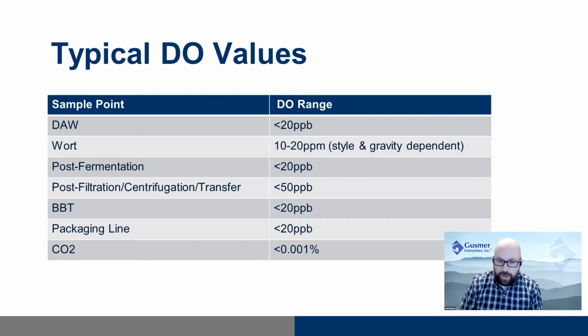So for deaerated water and post-fermentation, both of those are less than 20 parts per billion. Those are ideal numbers. And like I said, the lower, the better. With wort, we're going to see anywhere between 10 and 20 parts per million, and that's going to be dependent on style and gravity of the wort, but also temperature and pressure. So your brewers might have a harder time getting that oxygen to dissolve because you're pumping back at a lower temperature. So something to keep in mind.